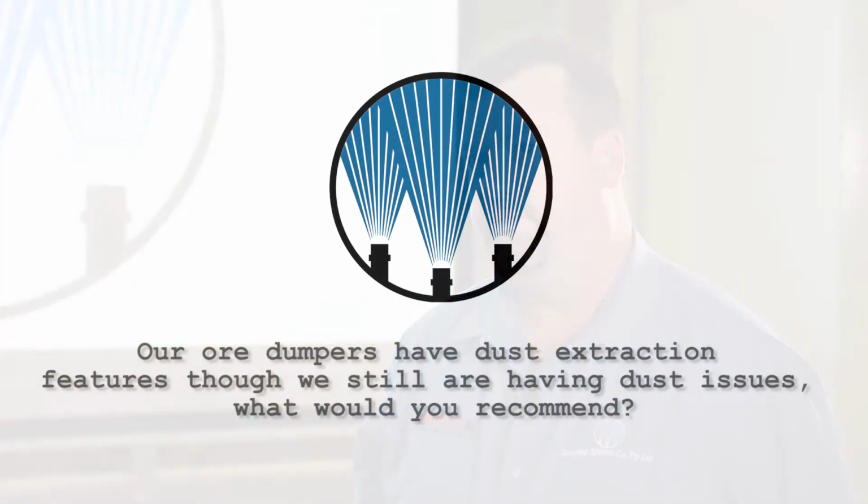For ore moisture, you've got to analyse it as a whole site. You can't just say which sprays to use. You've got to look at the whole site, look at where the conveyors are, how much ore's travelling on there, and what the moisture content is as it starts. Then work out what your dust suppression sprays are going to be across site. Once you know your dust suppression sprays, you take that out of the factor, then you add in your dust prevention sprays, which usually keeps within the limit of what they specify on site, which is averaging around 6%.